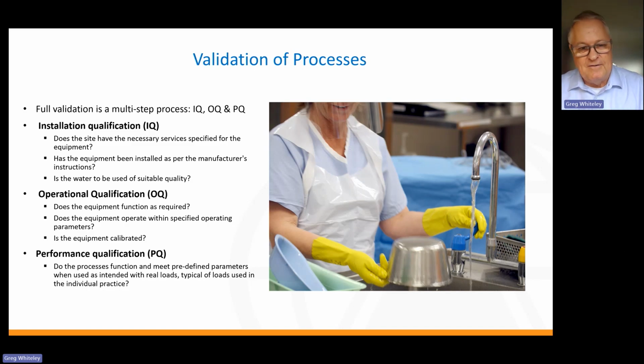But when you get into the technical detail, you find there are at least 3 steps. So if you've got a new device, there's a thing called installation qualification. To my simplistic way of looking at it, that's just turning the damn thing on and making sure that it works, particularly with an automated process. Then there's operational qualification. That's getting a technician probably to make sure that it actually does work and running a couple of cycles on it. And this applies whether you're using an automatic endoscopic reprocessor, a washer disinfector, or a sterilising device of some sort. And then you get to this thing called performance qualification. Now, most of the time, IQ and OQ will be done by the technicians that install these devices, but PQ is probably the most important factor, because that's where someone has to take your standard approach and test that it's working with your standard approach.